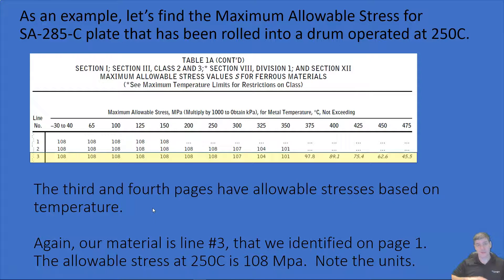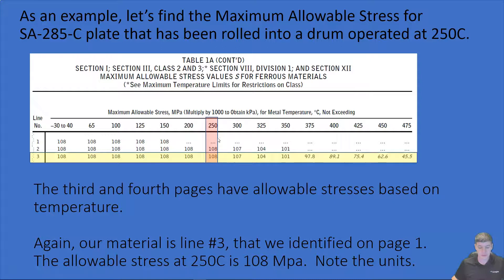Now we flip to pages three and four, which are a continuation of each other and tell us the allowable stress for the material. We continue on line number three and look for where it matches our temperature. At 250°C we have an exact match in the table, which tells us 108 MPa — that is our maximum allowable stress in MPa.